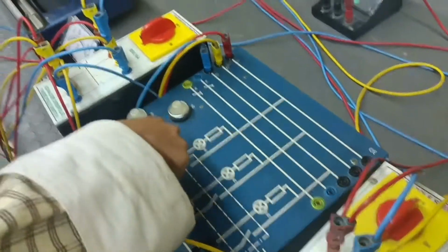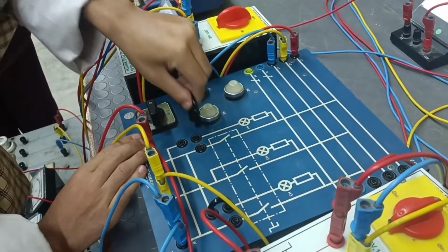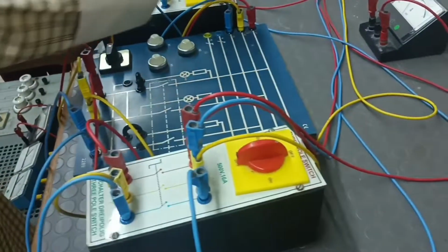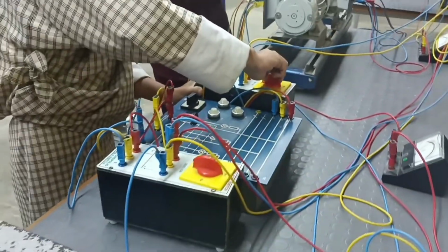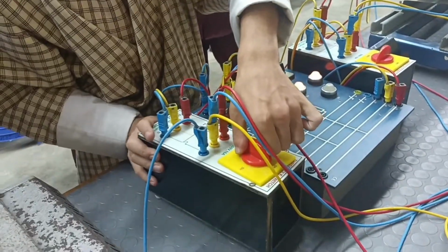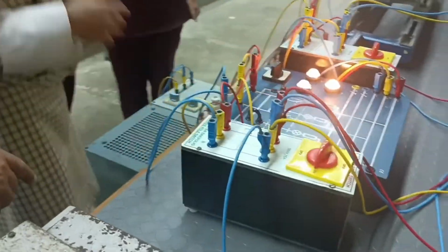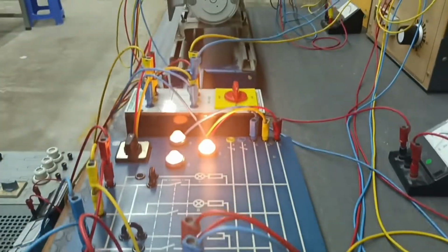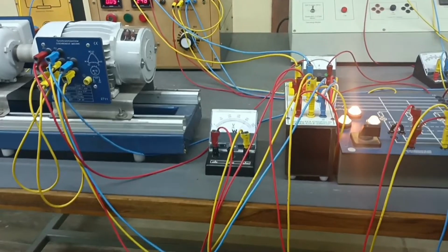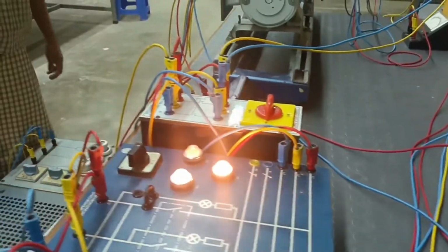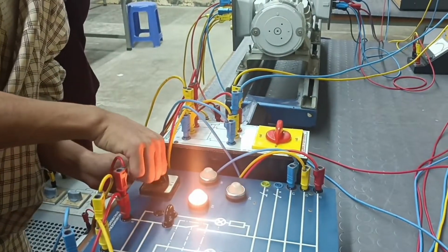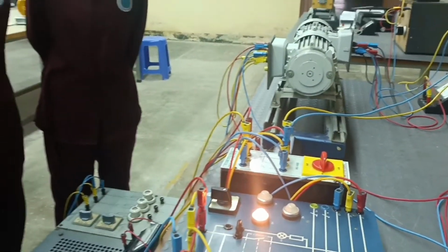Next, we use the 2 dark and 1 bright method. First, we turn on the switch at the incoming generator, and next we turn on the switch from the bus bar. Similarly, to slow down the speed of the rotating lamp, we regulate the voltage at the incoming generator, and then try to switch on the synchronizing 2 dark and 1 bright phase.